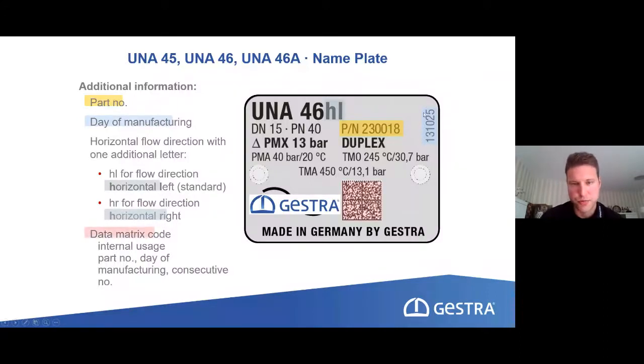So we will have a part number here at this part, the manufacturing date. So when was it produced? We will have the maximum differential pressure for that kind of steam trap, and this here tells us what's about our control unit. Does it have this automatic air venting capsule attached or not? If it has this capsule for air venting, then it's called a duplex. If it doesn't have that, then it's called a simplex. So here we're speaking about one with a membrane attached, so we are fine.